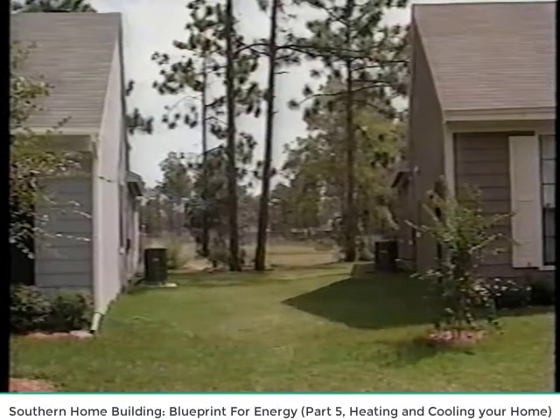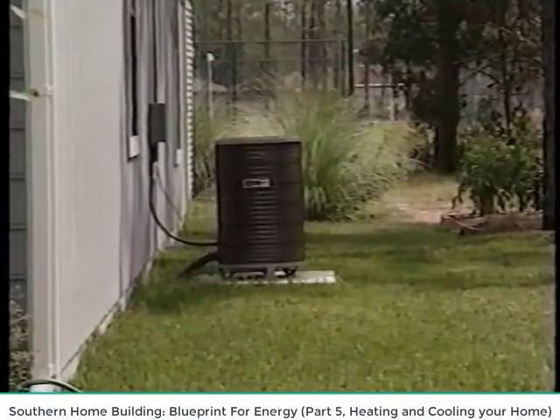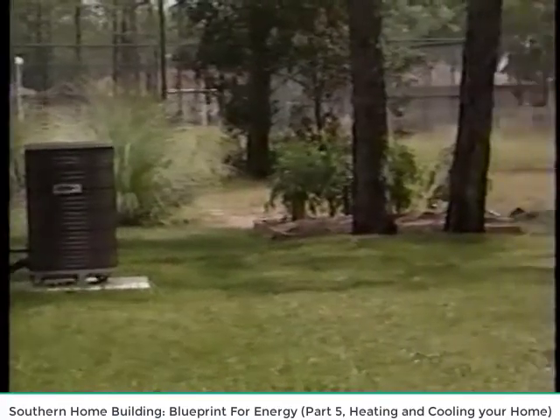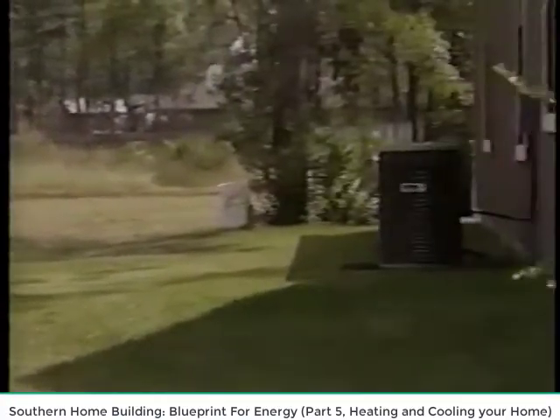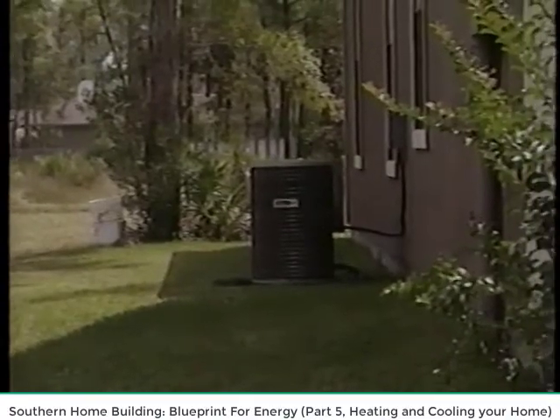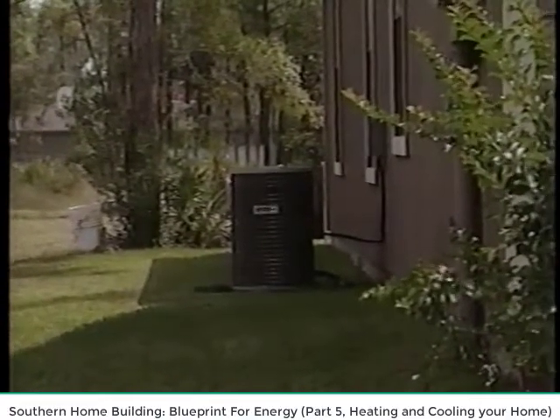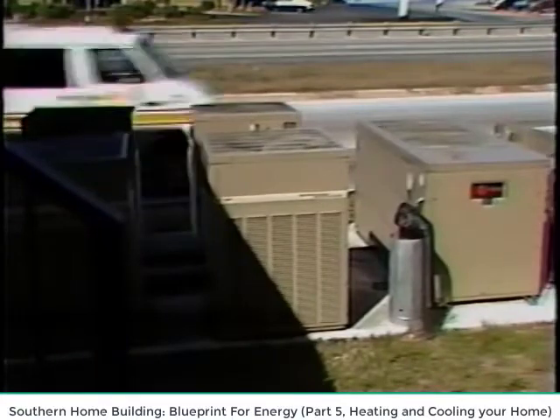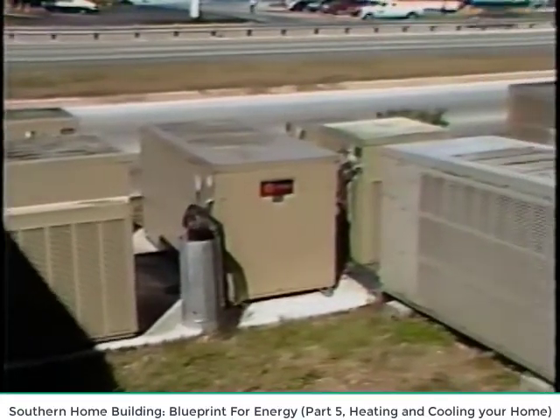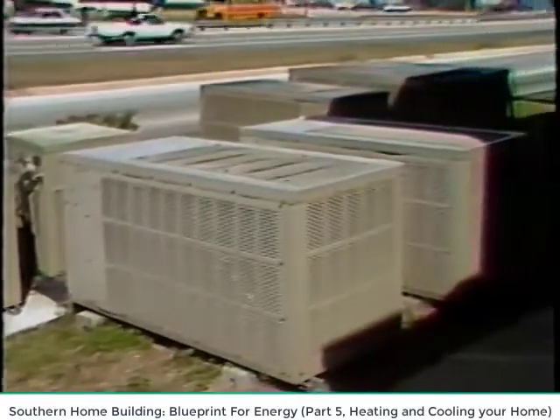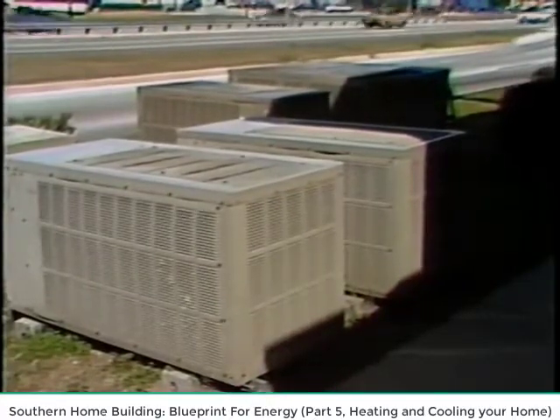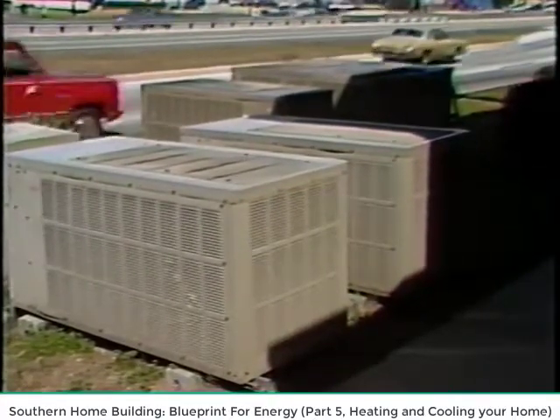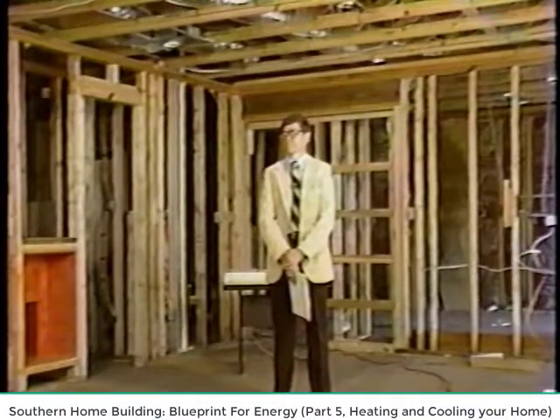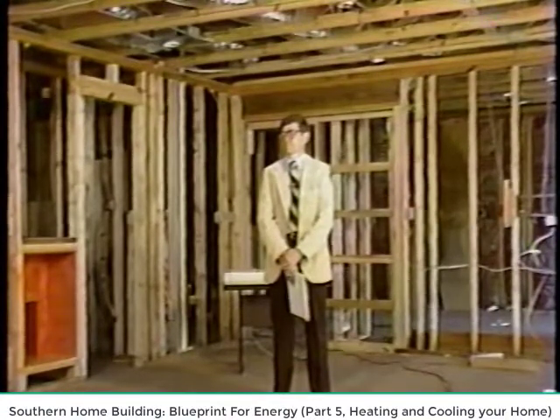The terms tons and tonnage refer to the cooling capacity or size of an air conditioner or heat pump. 2 or 2.5 ton heat pumps may have been considered too small for homes built a few years ago, but many energy-efficient passive homes now require these small units. Bigger is not better. A very simple engineering calculation, and not guesswork, should be used to determine the correct size of the air conditioner or heat pump. Air conditioning contractor and mechanical engineer Jim Adams explains.